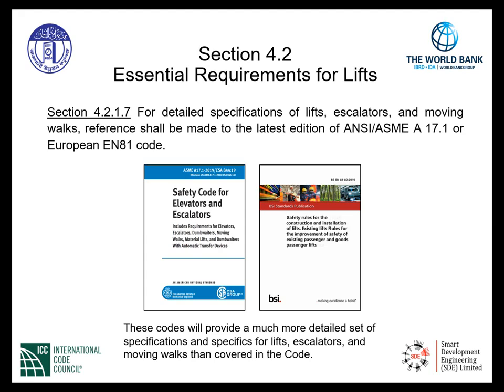We have reference standards. Section 4.2.1.7: for detailed specifications of lifts, escalators, and moving walks, reference shall be made to the latest edition of the ANSI ASME A17.1 or European EN 81 code. These codes will provide a much more detailed set of specifications and specifics for lifts, escalators, and moving walks than covered in the code. This is where we get more specific with the mechanical and the electrical and many other dimensions regarding the design and installation of lifts, escalators, and moving walks.